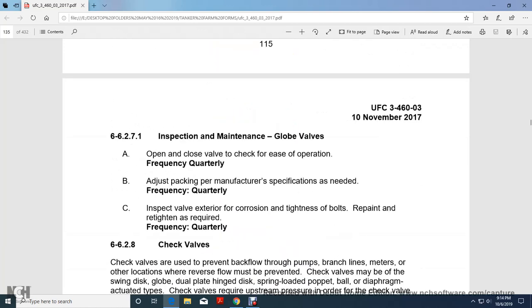Inspection and maintenance, globe valves. Open and close with a check of the ease of operation quarterly. Adjust the packing per the manufacturer specification quarterly. Inspect the valve exterior for corrosion and tightness of the bolts, repaint and retighten quarterly.